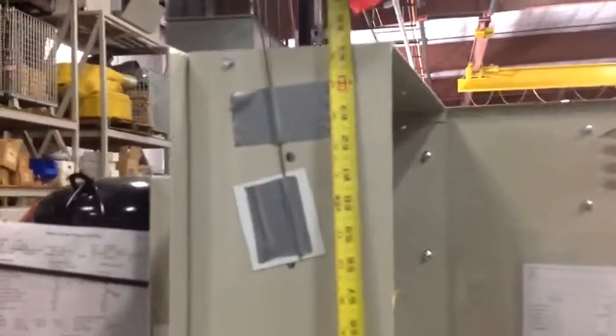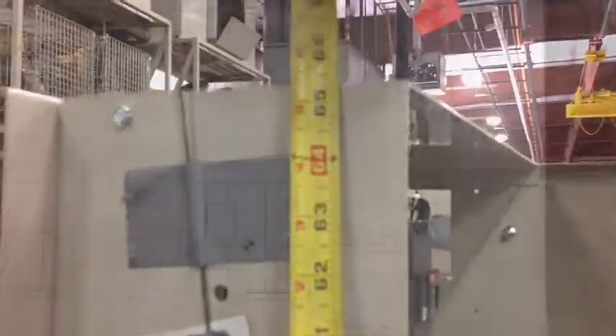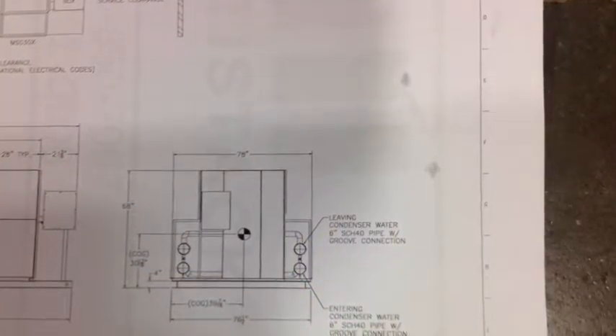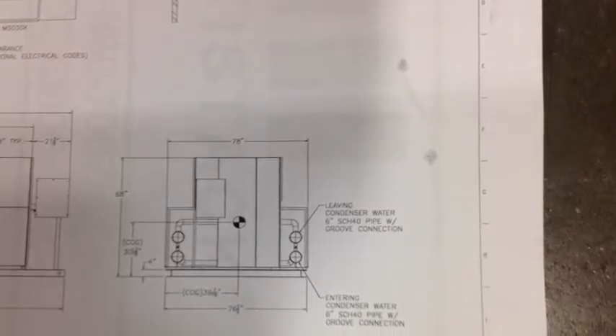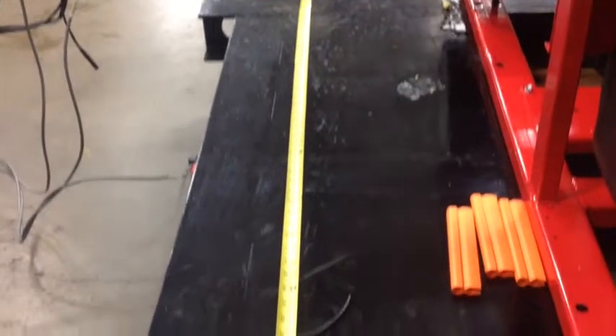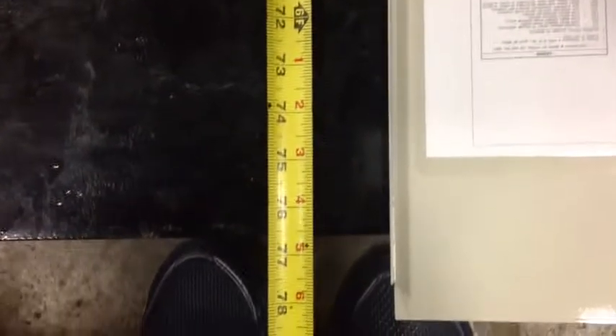Now showing you the overall height, including the 4-inch lifting frame, just above 65 inches. On the drawing it shows 68 inches. That accounts for our cabinetry that will be field installed after startup. This dimension shows the overall width of the unit of 76.5 inches.